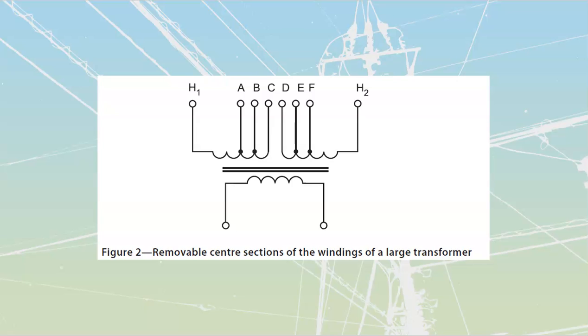Fault current is a massive amount of current that flows anytime the secondary gets completely shorted out. If something were to happen, like a wrench dropped across bus bars, that would cause a massive amount of current to flow on the secondary side, which would cause a massive amount of current to flow on the primary side as well.